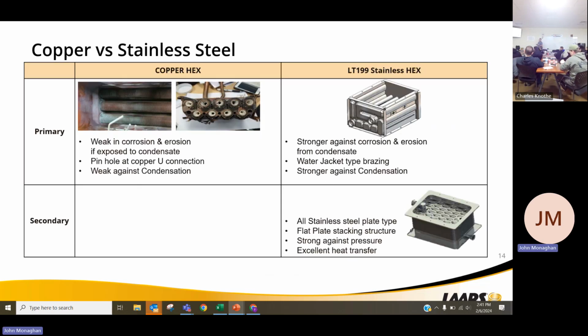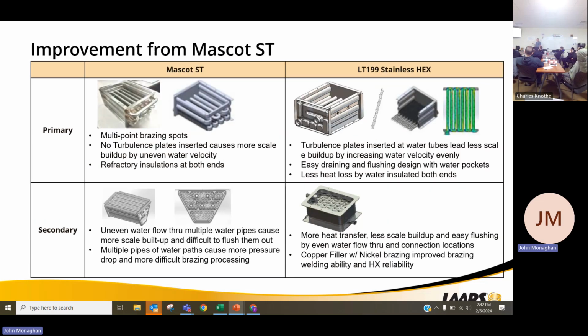Copper versus stainless. Copper is going to break down. It's going to be weak against the condensate, and this is a condensing unit. This unit is going to be fully stainless, so it's going to be more robust and stand up against any of the condensate that's going to be happening with it. So it's big improvements over our previous product.